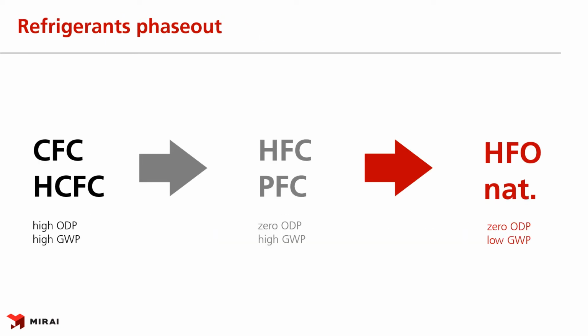Let's have a brief look at the refrigerants phase-out. Chlorofluorocarbons, CFCs, and hydrochlorofluorocarbons, HCFCs, were successfully replaced by hydrofluorocarbons, HFCs, and perfluorocarbons, PFCs, some time ago. This solved the high ozone depletion potential issue, but not the high global warming potential issue we are facing more recently. Hydrofluoroolefins, HFOs, and natural refrigerants are considered as the replacement for HFCs and PFCs. Please bear in mind that this summary is very generalized.